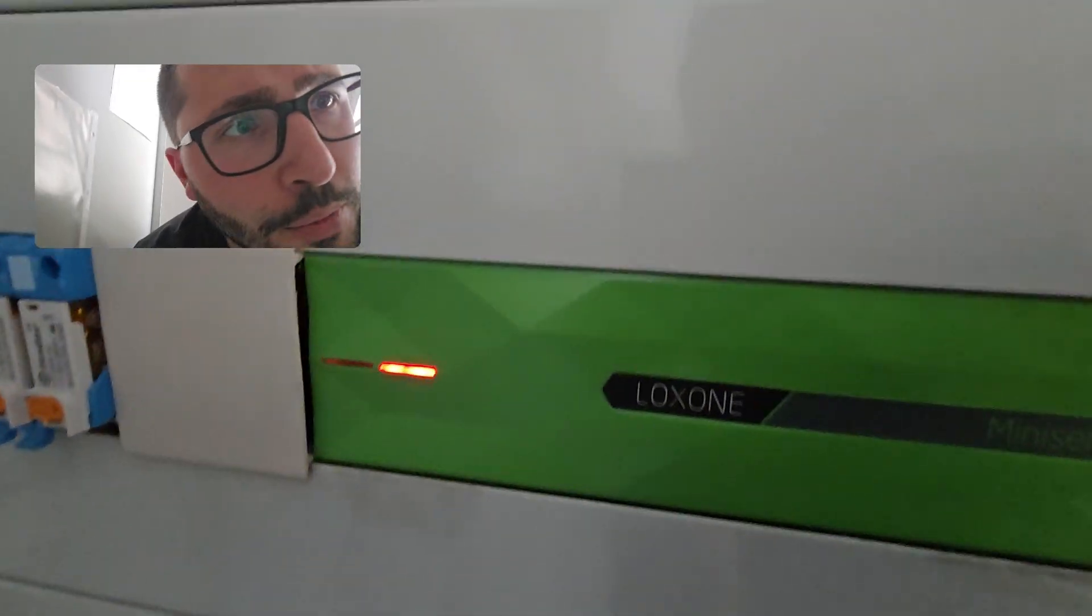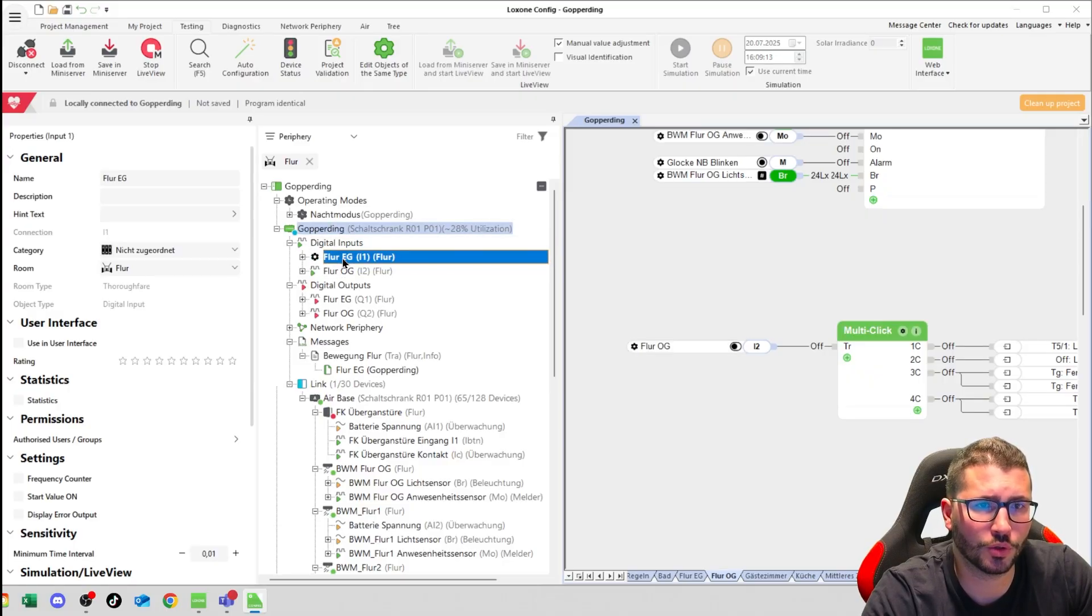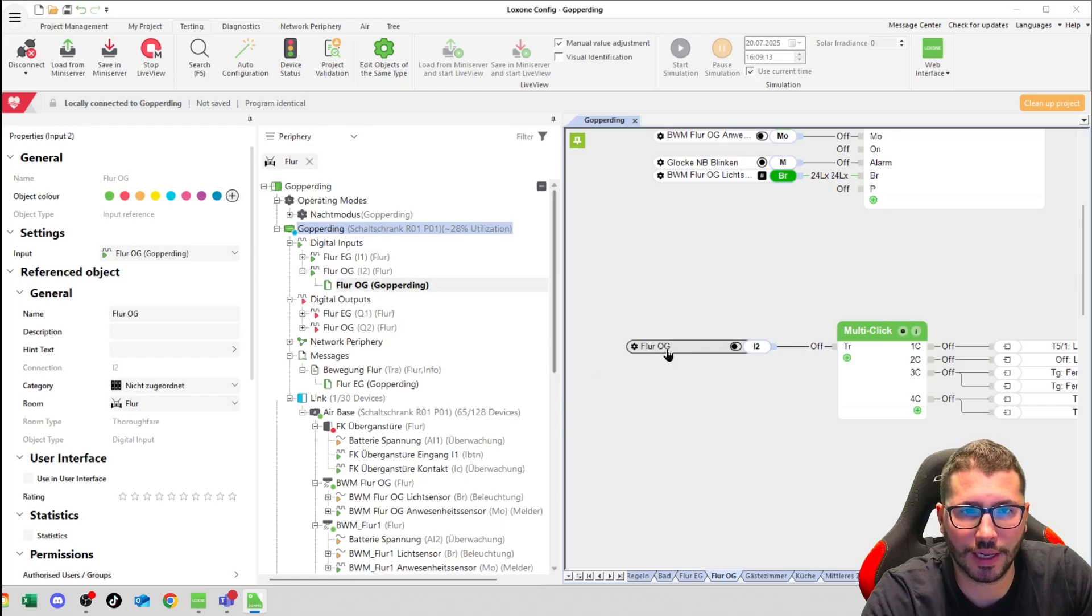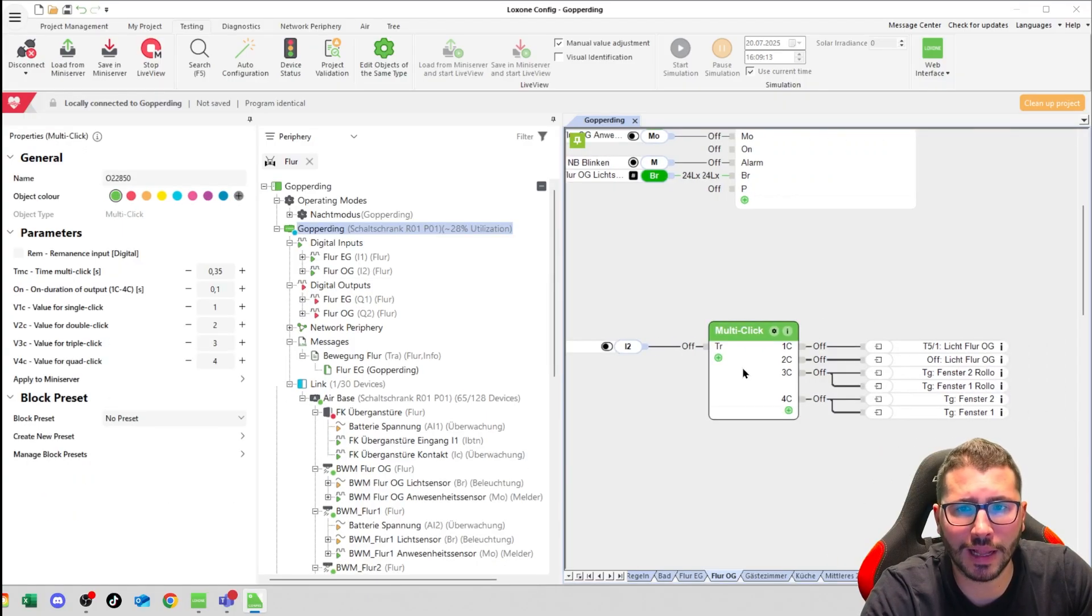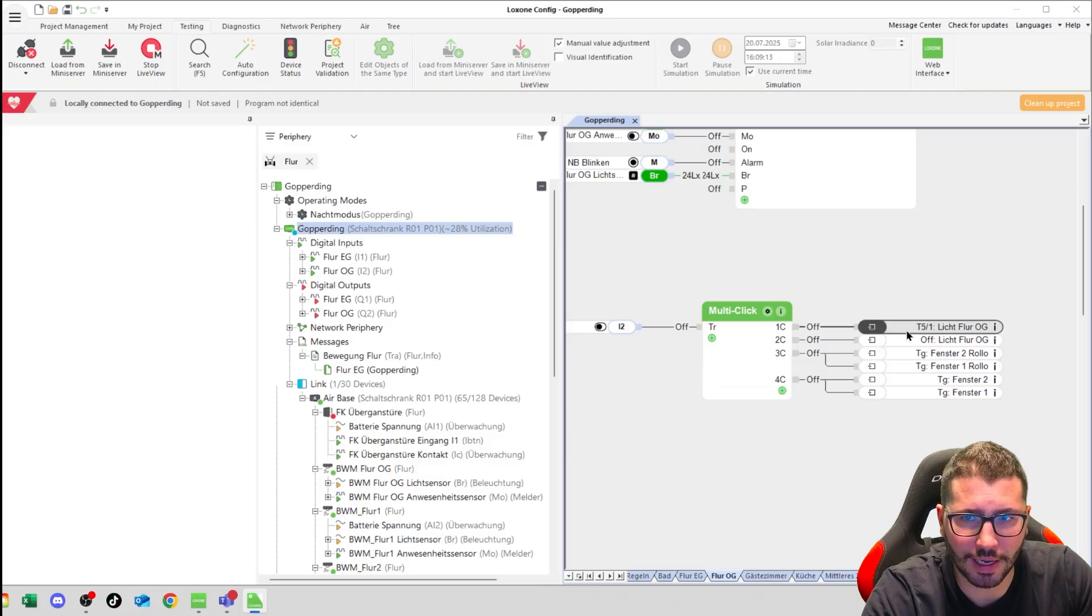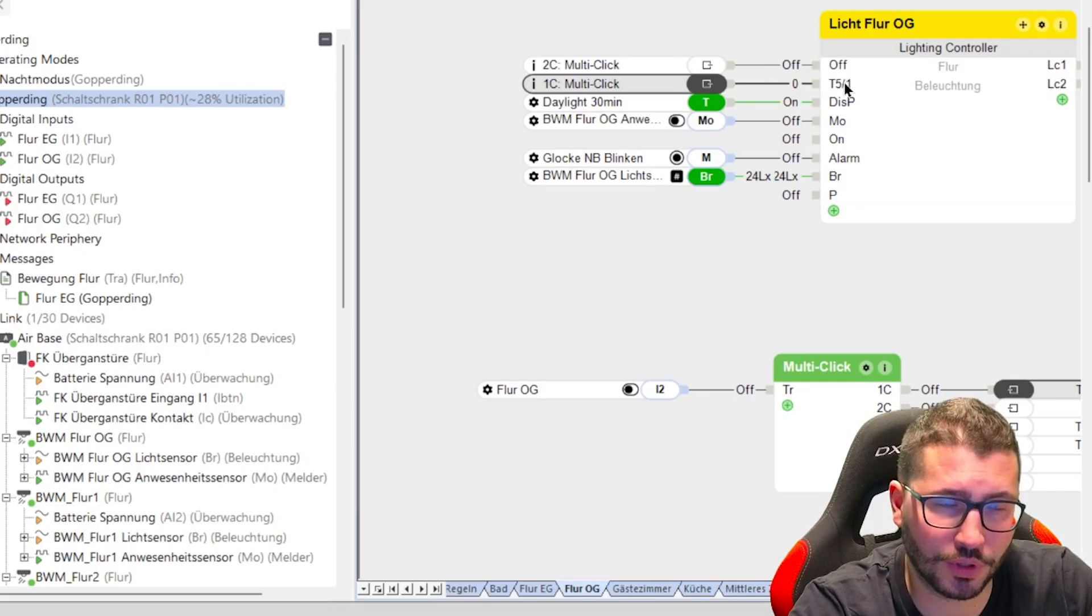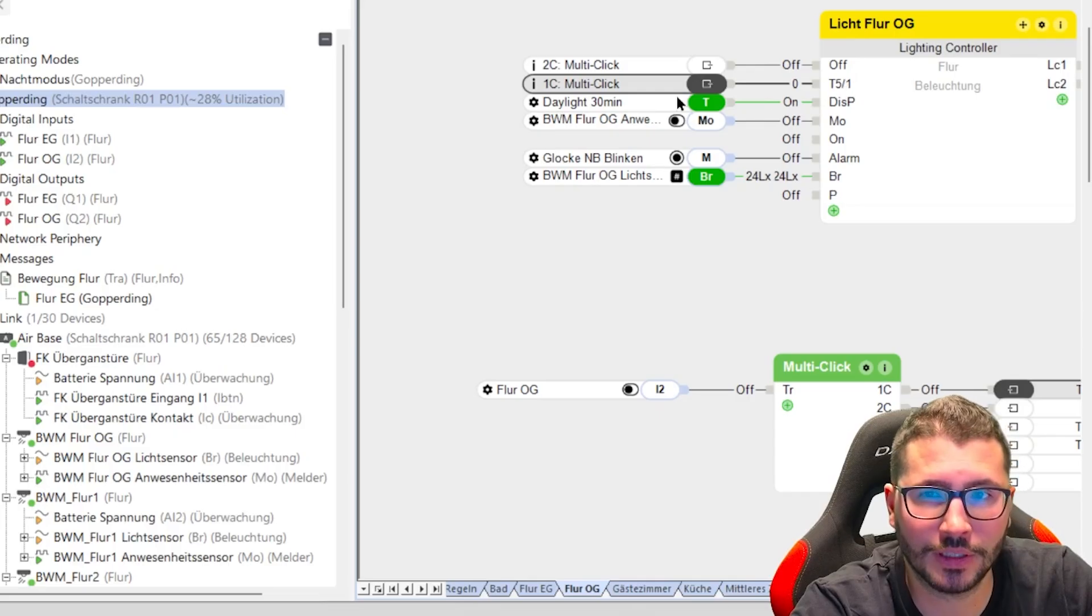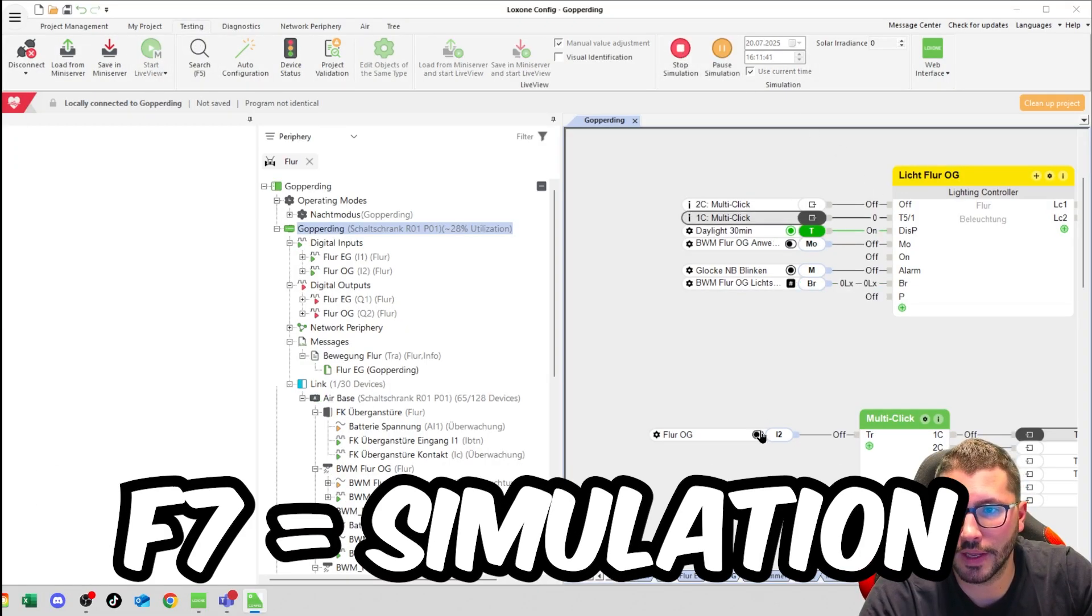Let me show you the config here on the mini server. I have my two inputs for the two push buttons, one for the ground floor, one for the first floor. I use the first floor one here on a multi-click function block. On a single click, I simply go on to my T5 input. Yes, you can do this without having a Loxone push button. If I now simulate it, you can see...